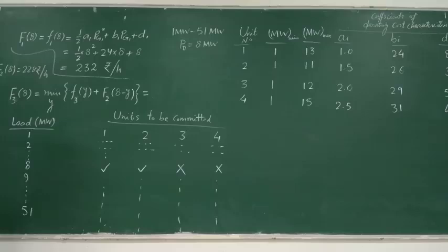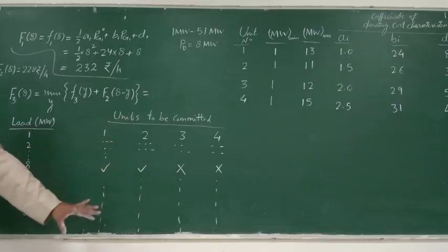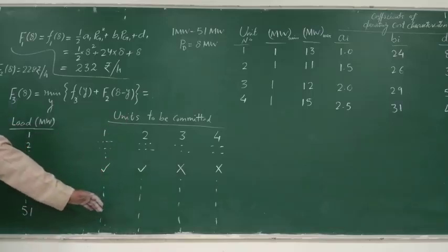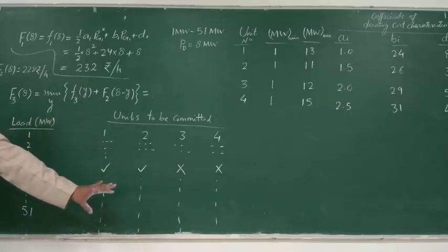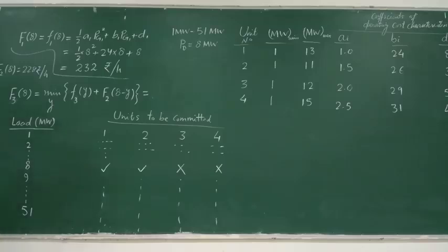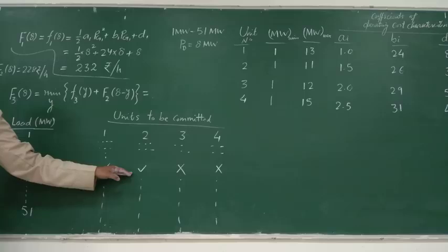Is it clear till here? You know what this is? This is the optimal unit commitment table. How is it prepared? We discussed just now. So once the UC table is prepared, once only for a particular plant, you know the range of load that can be met by that power station. So at any moment of time, just sense the demand at that moment and compare with this, and the corresponding units will be selected. Is not it? This is step number 1.